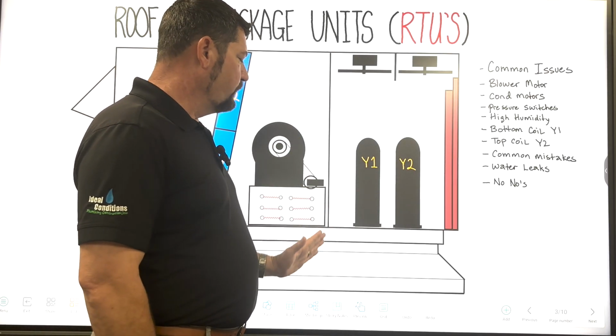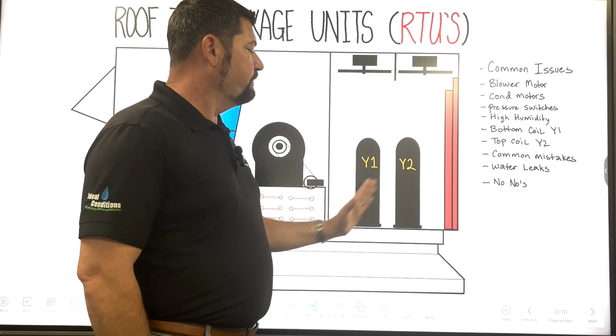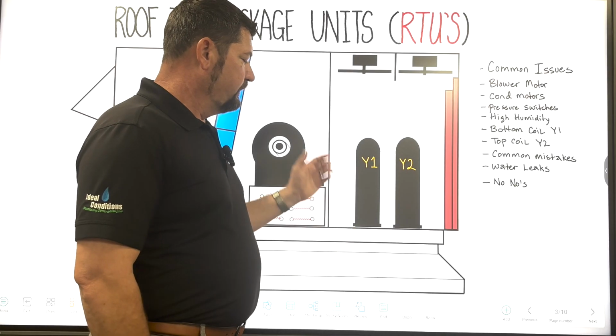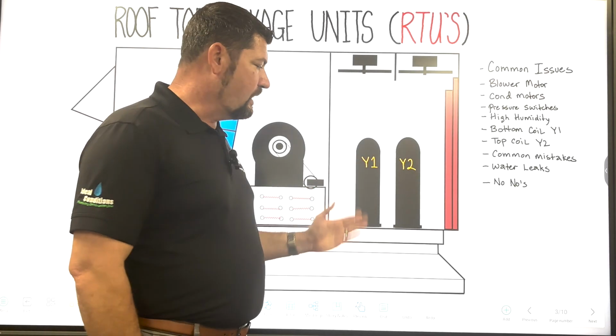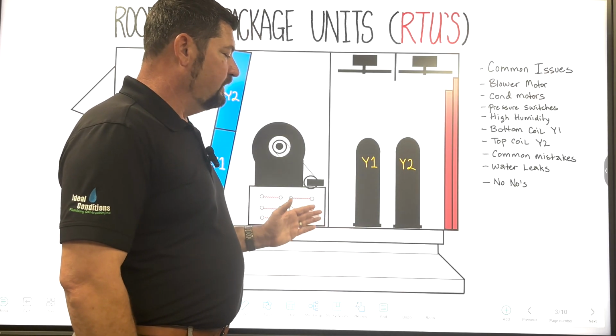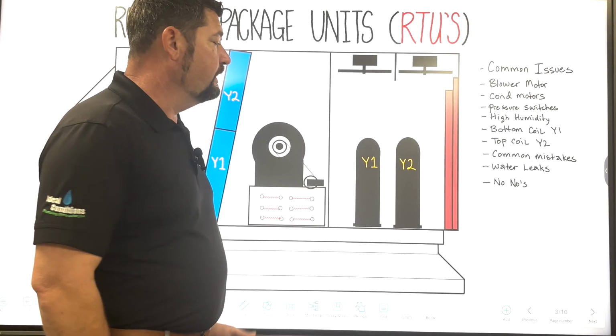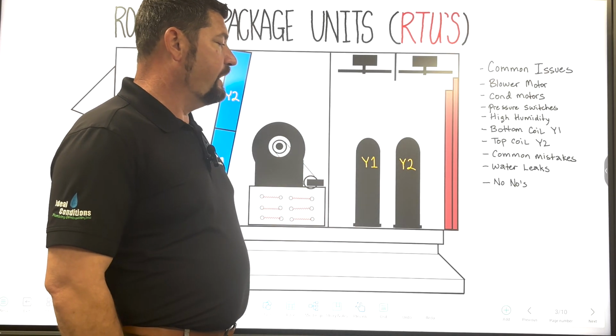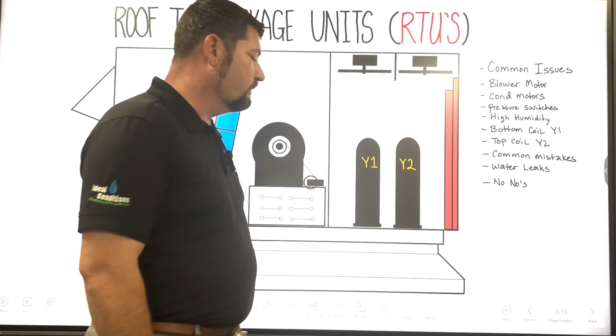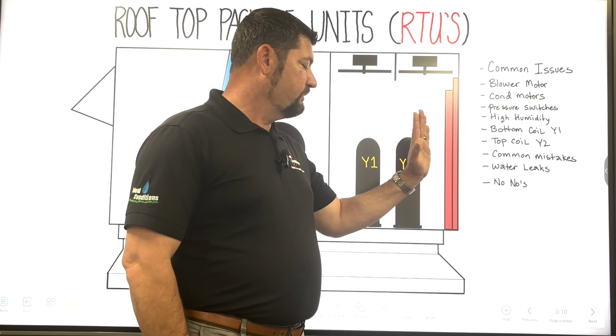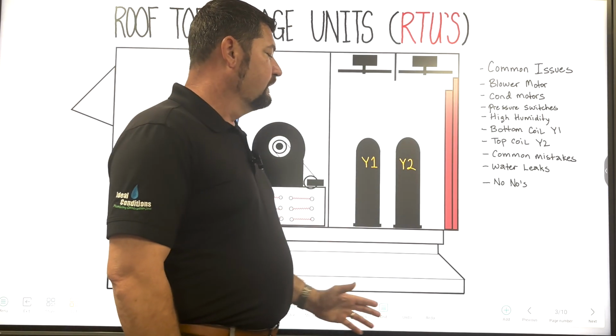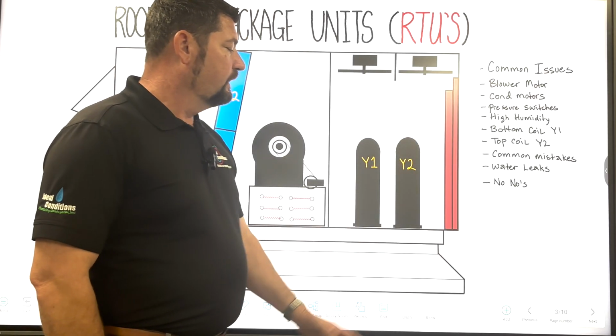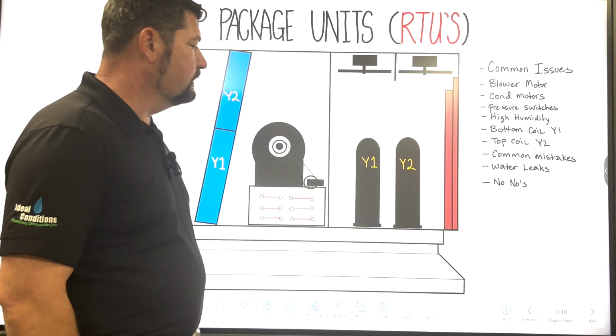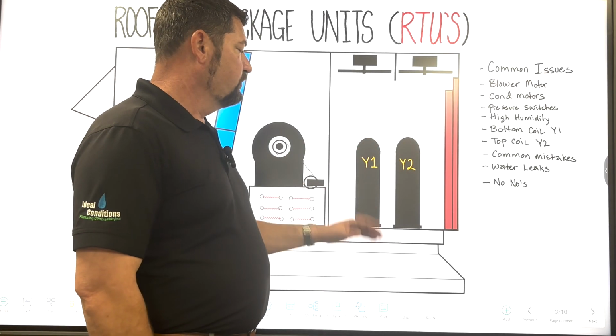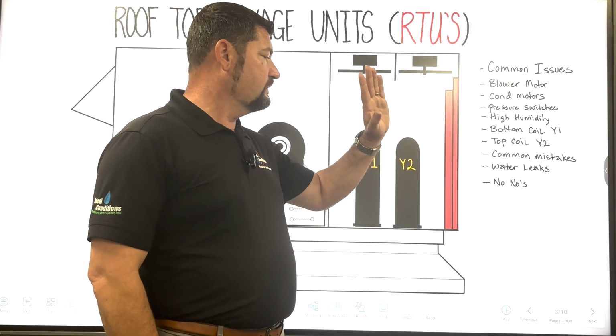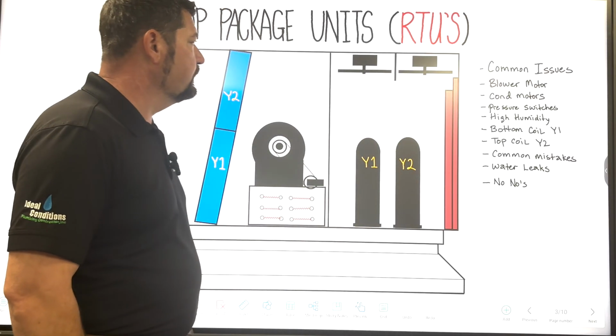You should never ever go into the condenser section of the rooftop unit and drill a hole into that thick steel bottom to run your electrical whip into. That is not the correct way. That is not what the manufacturer intended, and that is never going to work long term for the customer. It may not even work right away. As soon as it rains or water pools up in there, you're going to have issues. So the no-nos are basically what we're covering right now. Disconnects should be on these units. Electrical whips should be either coming up through the blower section or coming up through a gooseneck on the roof, and then whipped over into a side of the unit where you can safely secure a disconnect box to where you're not going to harm the functionality of the system. It can still be serviced and you're not going to poke a hole in the coil or whatnot.